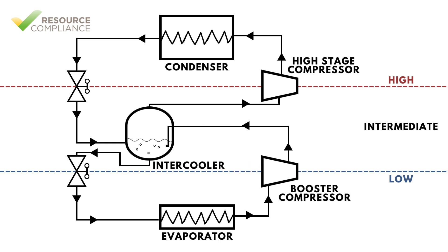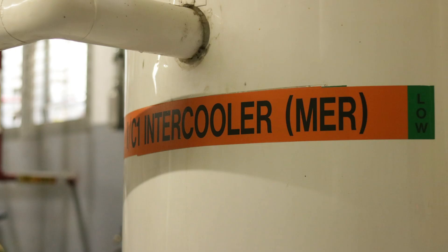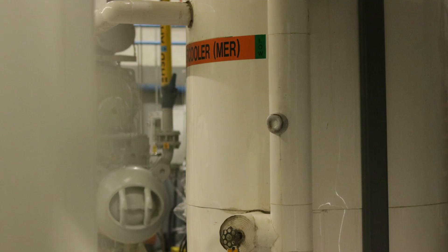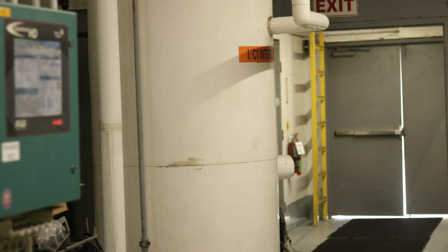Vapor exiting the booster compressor is piped to a vessel called an intercooler. The intercooler maintains a level of intermediate pressure liquid that the booster discharge gas percolates through. This de-superheats the booster discharge gas so that the vapor exiting the top of the intercooler, while at the same pressure, is a much lower temperature.